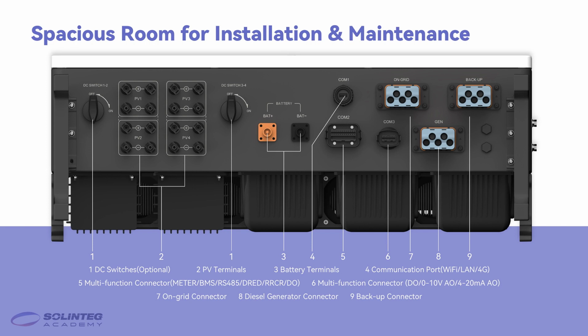Let's see the bottom connectors. From left to right is the DC switch. There are 2 DC switches to control the different MPPT trackers. And this is the PV terminals for connecting solar panels, the battery terminals for connecting battery, and the COM1 port for connecting the communication modules. The COM2 port is a multifunctional connector for connecting meter, the battery, RS485, DI, DRM, CT, and 1 DO connectors. We have added a COM3 port as a multifunctional connector, the DO and AO, to intelligently control the smart loads. There are 3 output ports: on-grid, backup and the diesel generator.